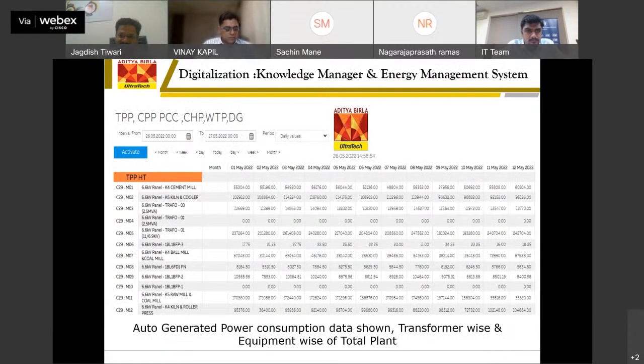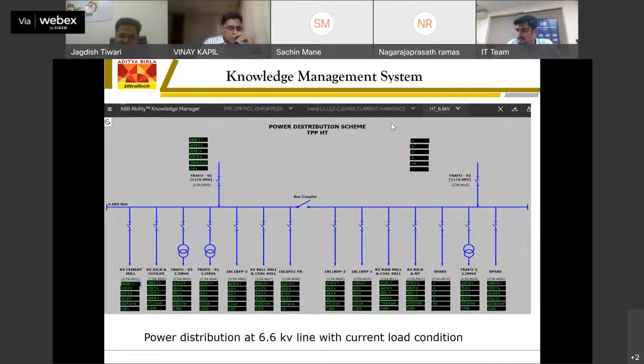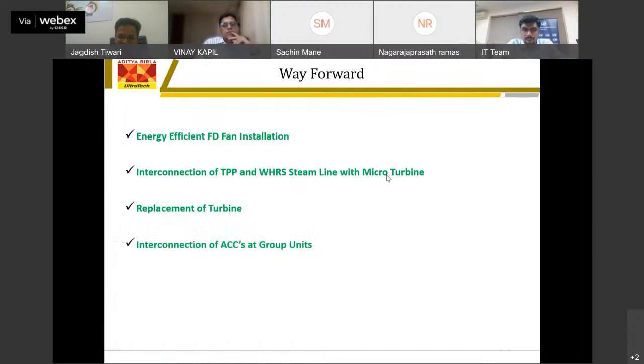And apart from that, we have a knowledge manager and an energy management system. In the knowledge manager, we are monitoring the parameters accordingly. We are tuning the PID, and this is a glimpse of the knowledge management system. Now coming to the way forward, sir. Further, we have targeted heat rate less than 2,900 kilocalorie per kWh and auxiliary power less than 5 on a yearly basis.